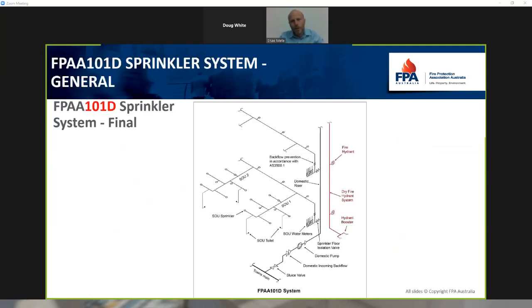So moving over to the 101D system, D for drinking, not domestic. It's actually the drinking water. We specify that it shall be off the drinking water supply rather than domestic. And the reason for that is it could be some of the reclaimed water or recycled water, and we don't want that. It's got to come from the drinking supply.